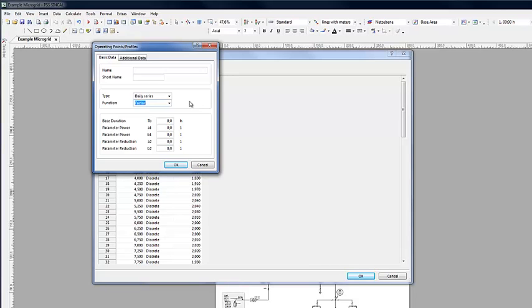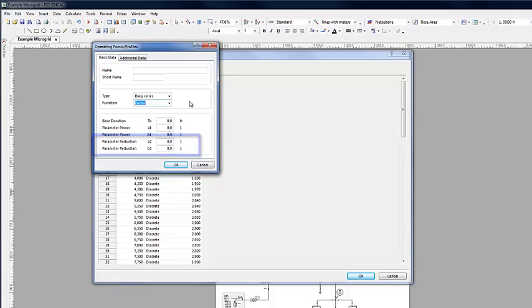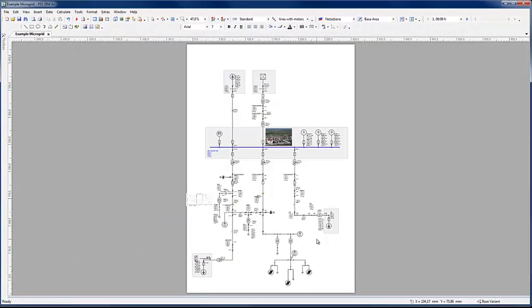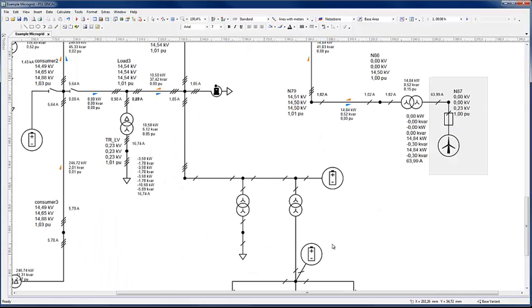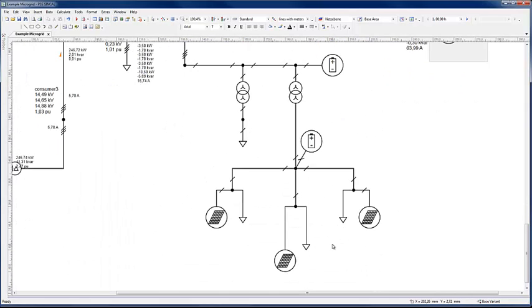Reduction factors are used to stochastically model individual consumption behavior, allowing PSS SINCAL to achieve a more exact load modeling in distribution networks. Reduction occurs only to consumers of the same type that are in radial subnetworks at the low voltage side of the same feeder.